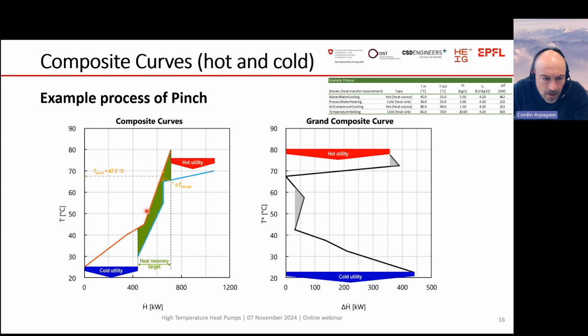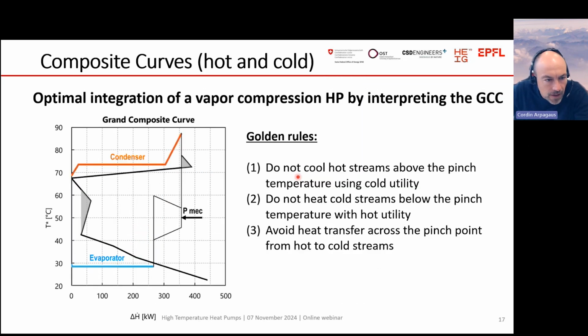By using these curves and taking the difference, we can find out the pinch temperature - in this case, around 70 degrees or so. So a heat pump could be integrated across this pinch temperature, as shown here. The condenser of the heat pump would be at 75 degrees, the evaporator at 30 degrees, for example. This would work and would be an energy-optimal integration for a heat pump.